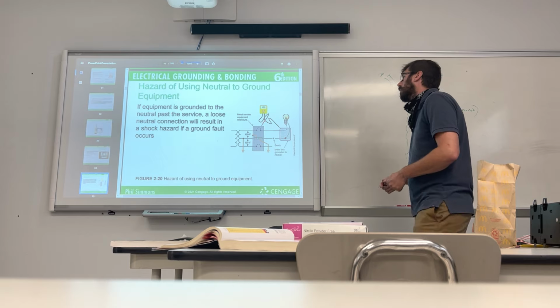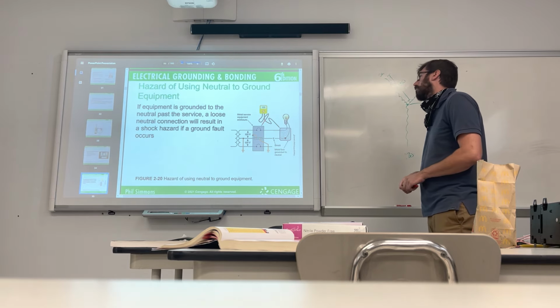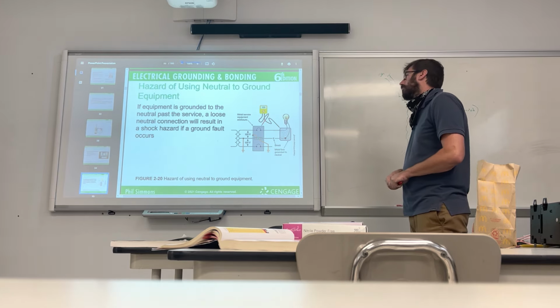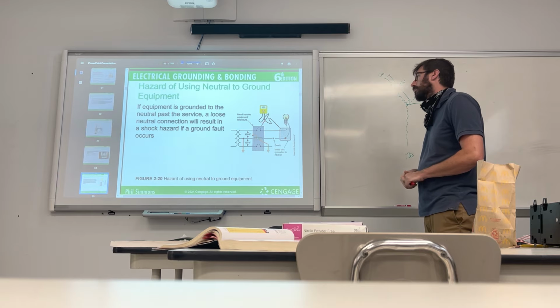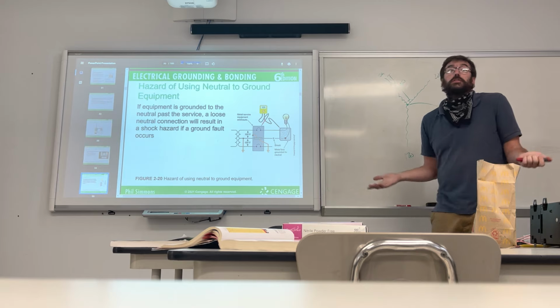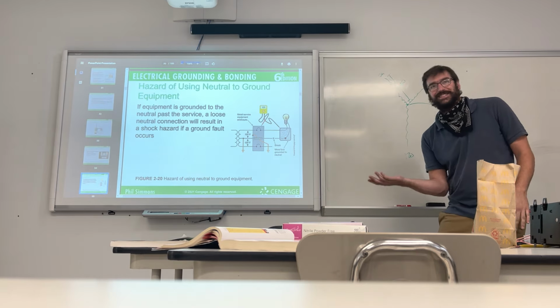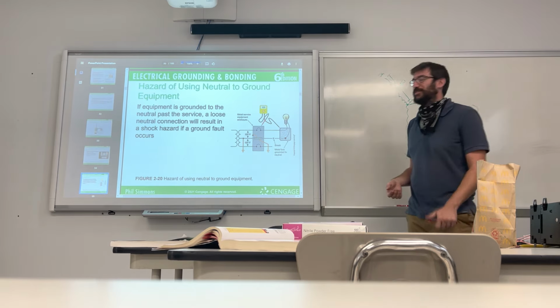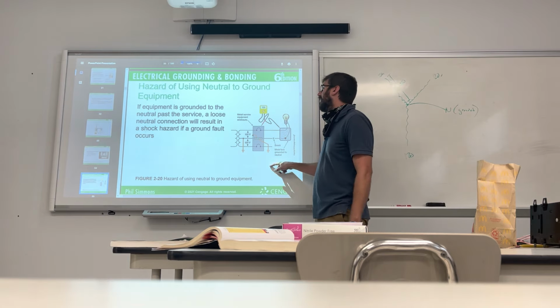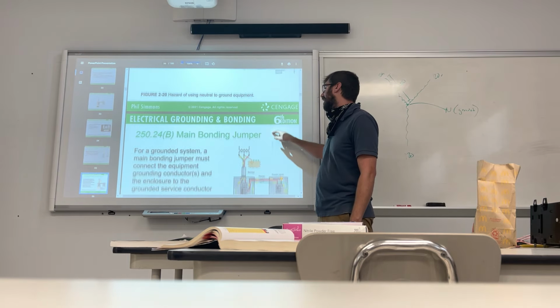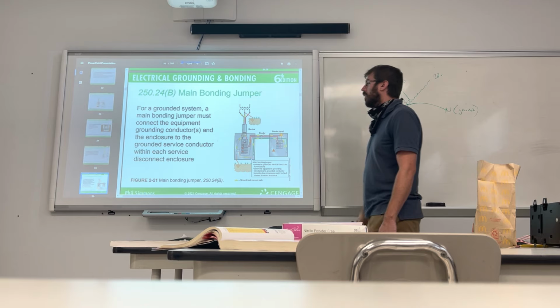Hazard of using neutral to ground equipment. If equipment is grounded to the neutral past the service, a loose neutral connection will result in a shock hazard if a ground fault occurs. Is there any shocking information there? Get it? Yeah, that was funny. I got a couple chuckles. Want to take this one too? Yeah.